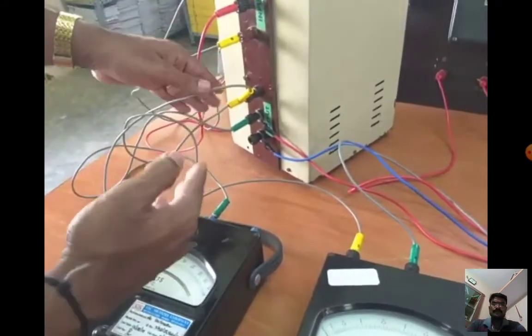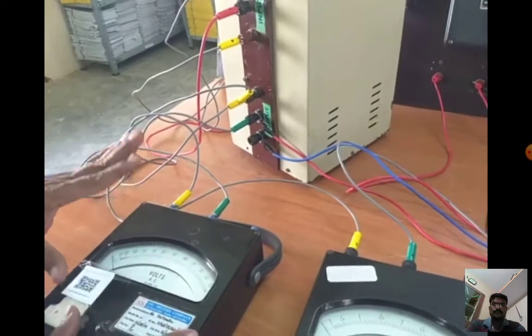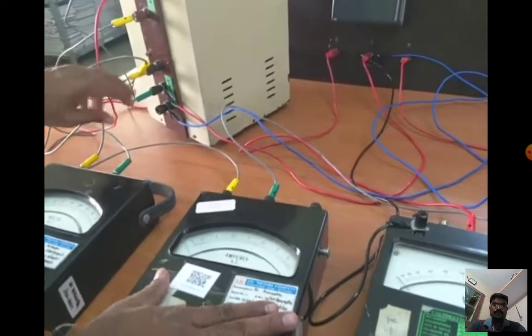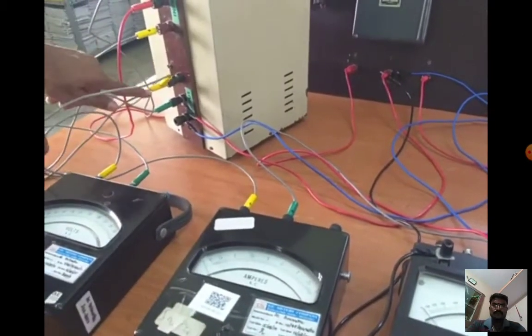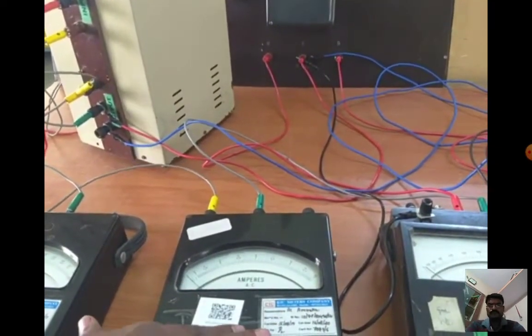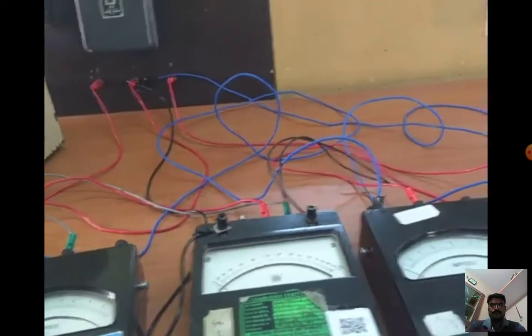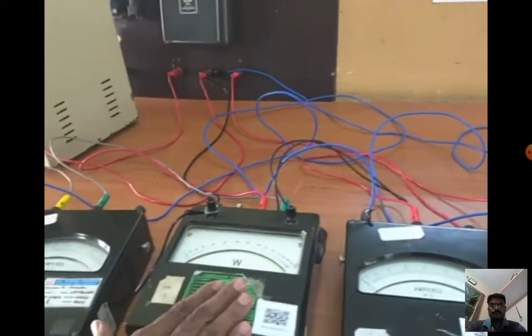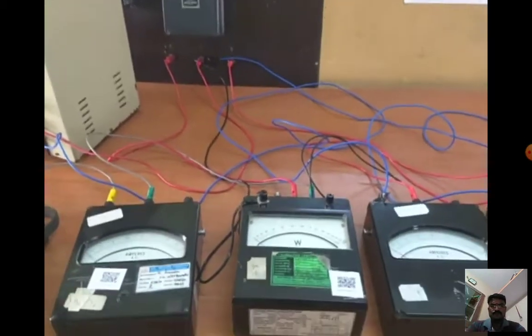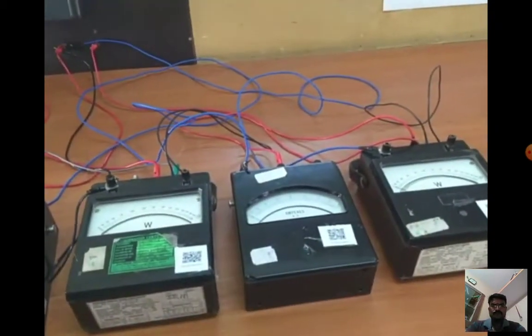First, we are connecting R and Y in parallel to the voltmeter, and the ammeter A1 is connected through the R phase. The R phase is connected through ammeter A1, and the B phase is connected to ammeter A2. Wattmeter W1 is connected between R and Y, and wattmeter W2 is connected between Y and B.